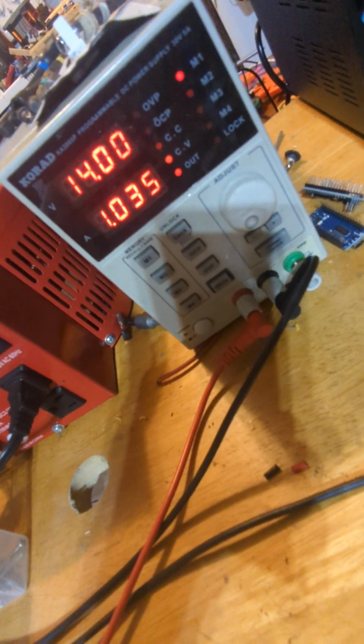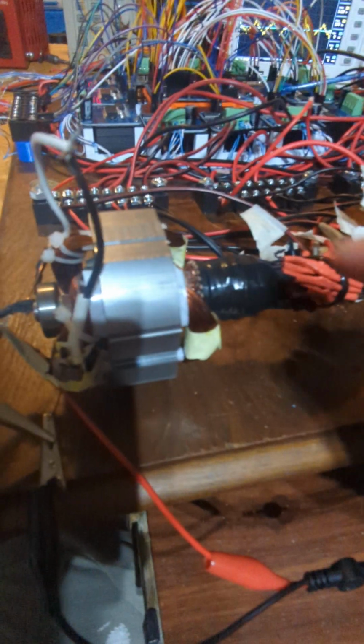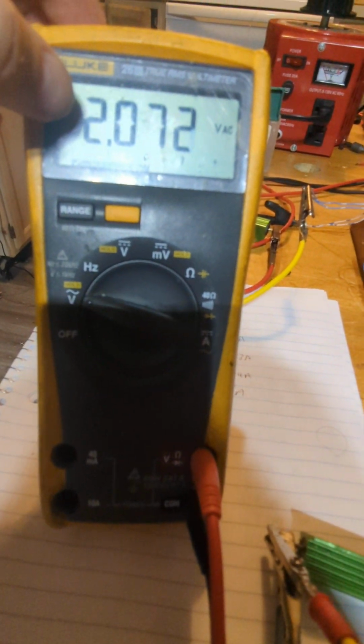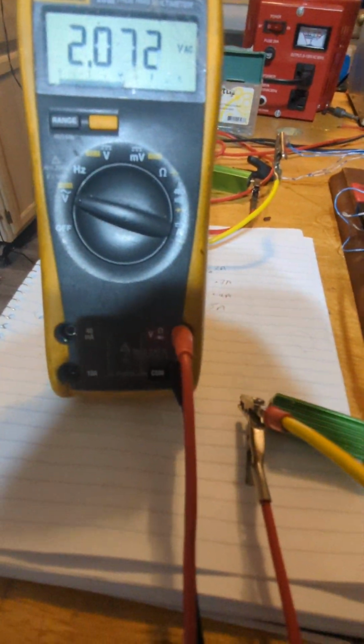Amperage is the same. Amperage barely changes no matter what speed we go. The quicker we go, the more power goes to the load. The slower we go, the less power goes to the load. Not only voltage, but current also, because this is a resistive load that follows Ohm's law. So if you want to know how much current is going through here, you work out Ohm's law with the amount of voltage going through there.